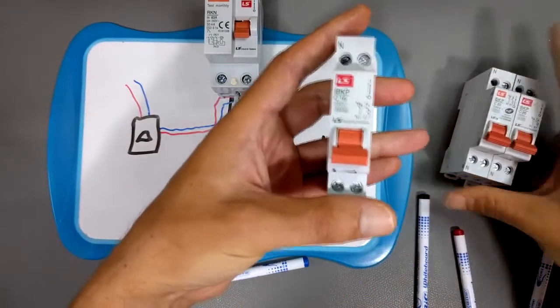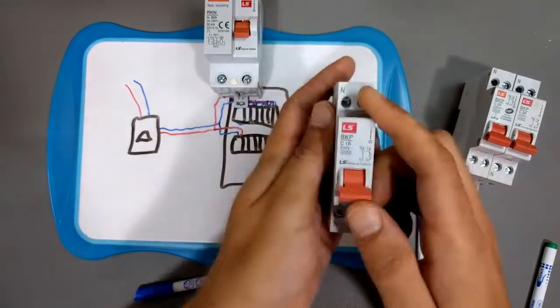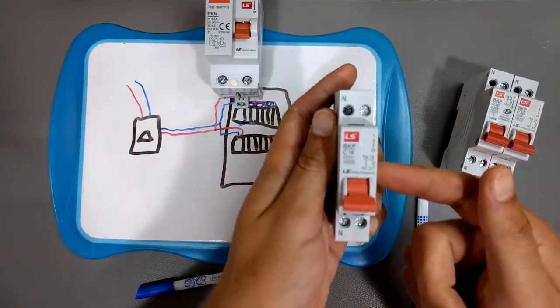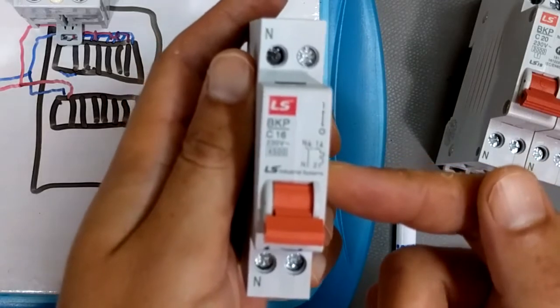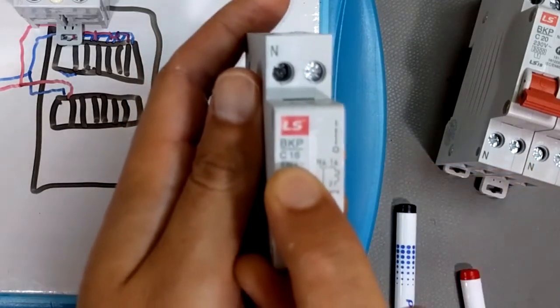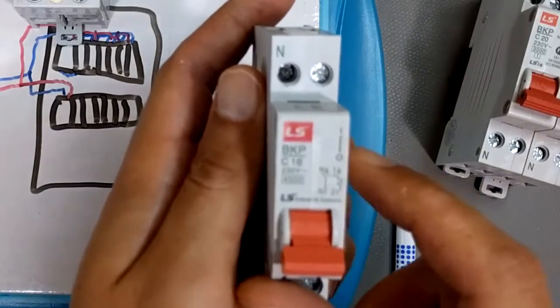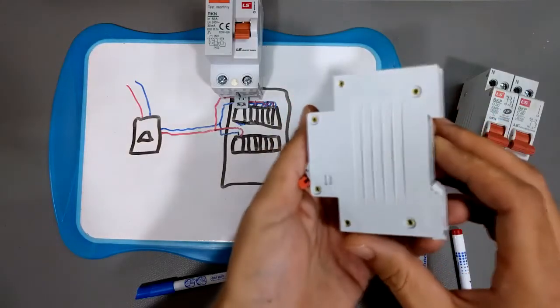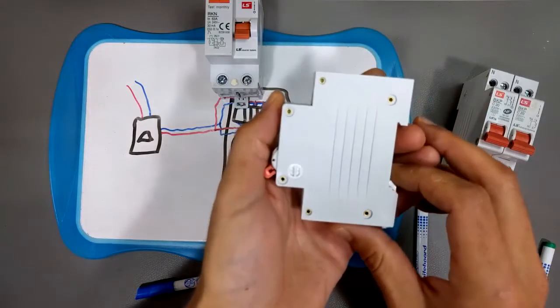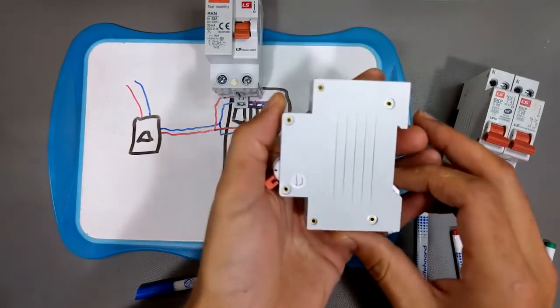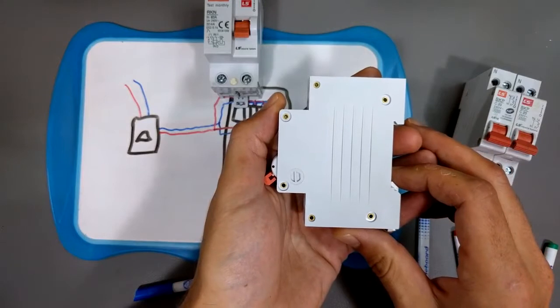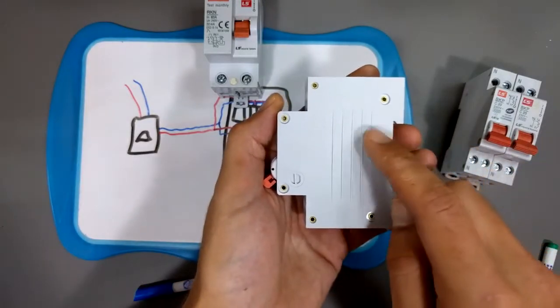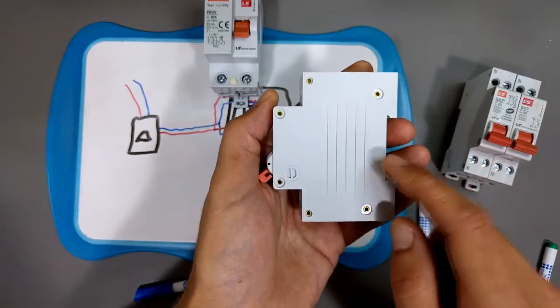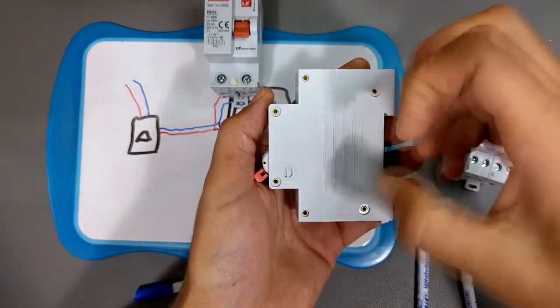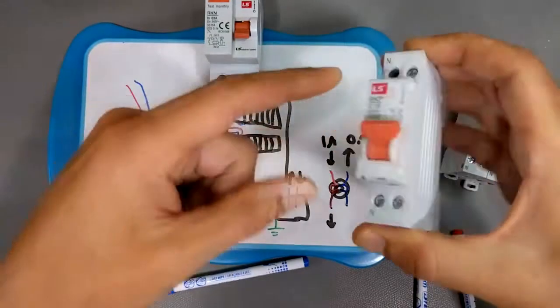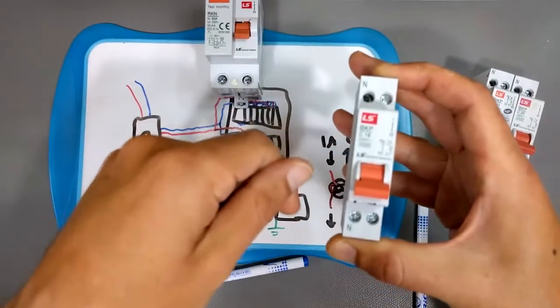Now these guys are typically a normal circuit breaker. It's on, it's off. Again, it's a light switch, but it has a purpose. It offers protection. In this case, it says C16, which means this is a 16 amp breaker. Now, at 230 volts, these are typically thermal magnetic circuit breakers. And what that means is that inside here, he usually has a coil. And if there's a very high current that goes through, that coil is energized and it pulls a little latch and this guy turns off.